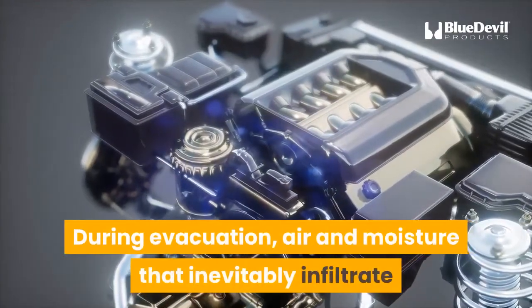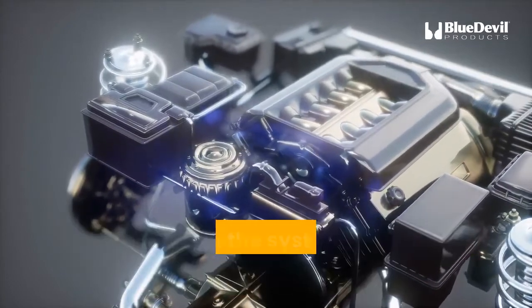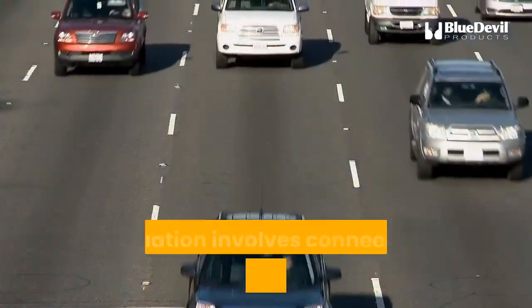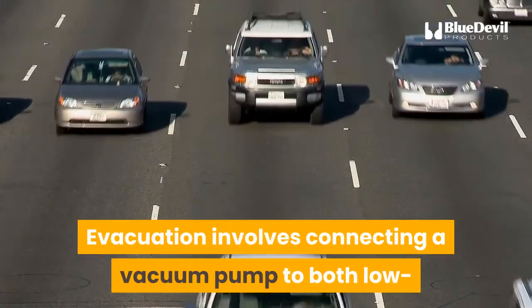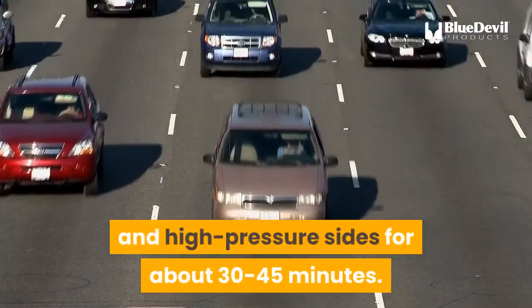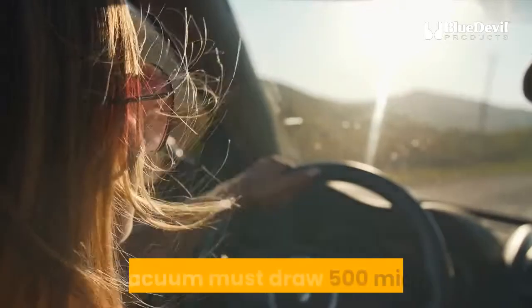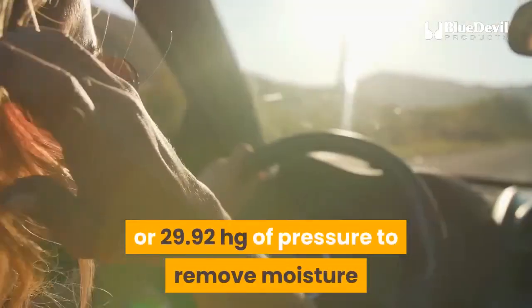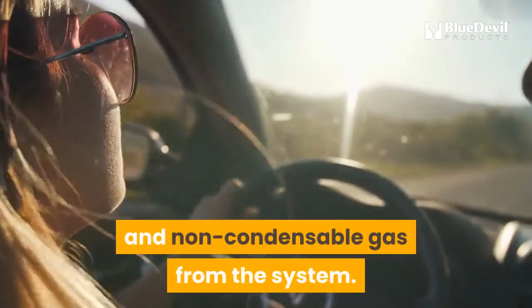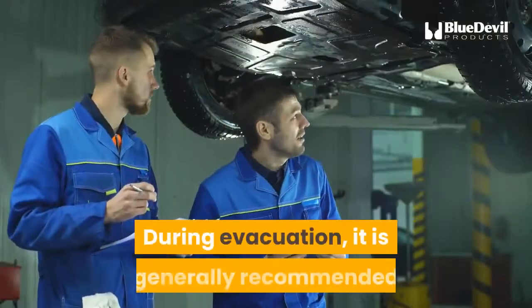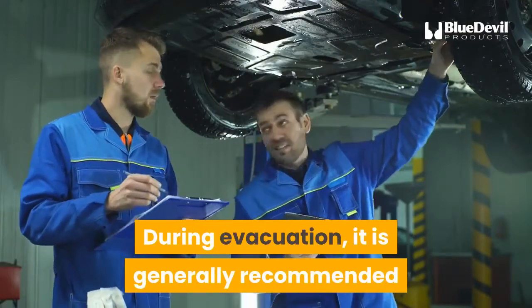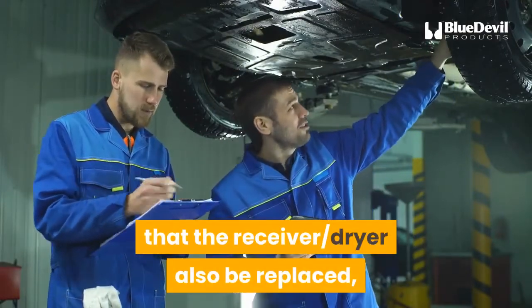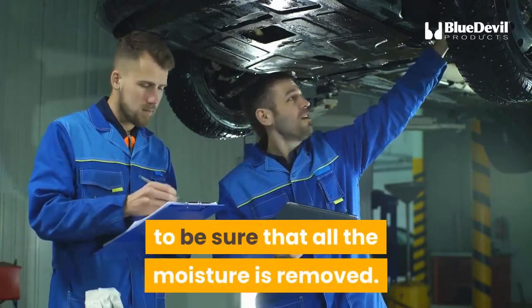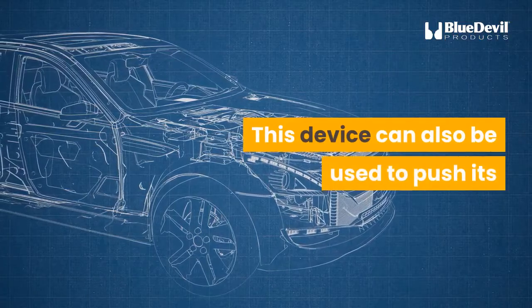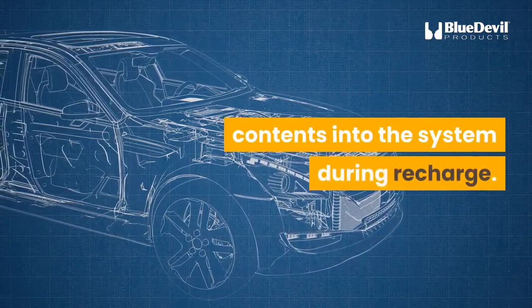During evacuation, air and moisture that inevitably infiltrate when the system is opened are removed. Evacuation involves connecting a vacuum pump to both low and high pressure sides for about 30 to 45 minutes. The vacuum must draw 500 microns or 29.92 Hg of pressure to remove moisture and non-condensable gas from the system. During evacuation, it is generally recommended that the receiver/dryer also be replaced to be sure that all the moisture is removed. This device can also be used to push its contents into the system during recharge.